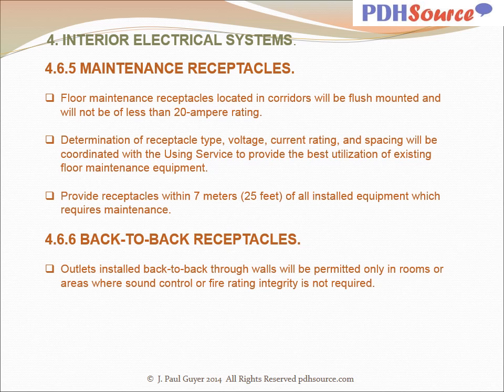Floor maintenance receptacles located in corridors will be flush mounted and will not be of less than 20 amp rating. Determination of a receptacle type, voltage, current rating, and spacing will be coordinated with the using service to provide the best utilization of existing floor maintenance equipment. Provide receptacles within 25 feet of all installed equipment which requires maintenance. Outlets.